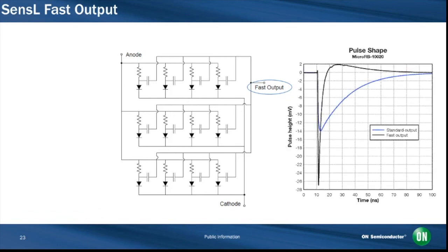The plot here shows a typical output pulse from the fast output, compared to one from the standard output from the anode cathode line. The fast output signal is particularly suited to fast timing measurements, using the ability to clearly distinguish the arrival time of the first photon in the pulse.